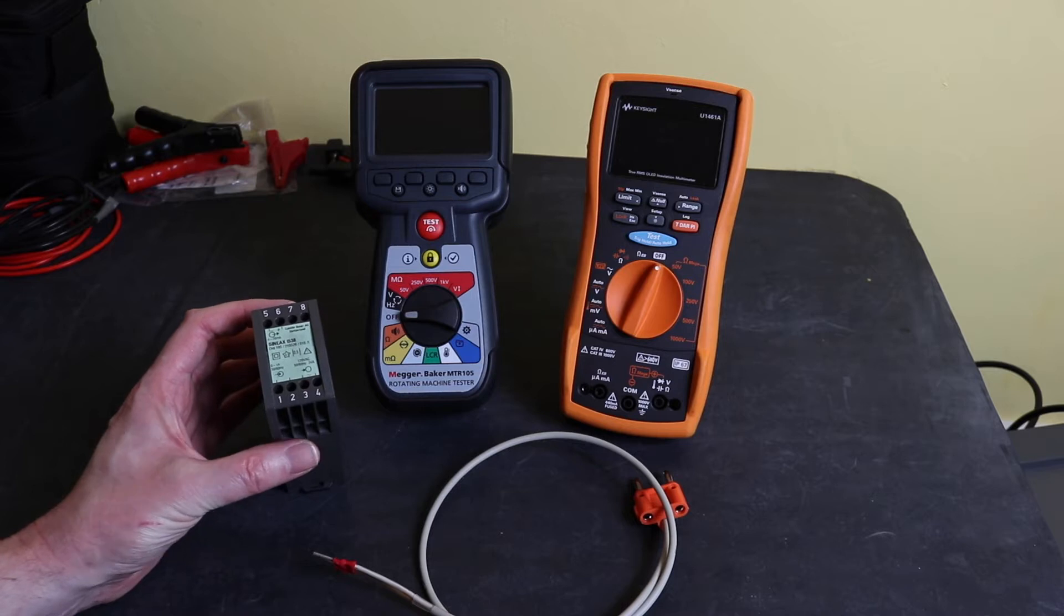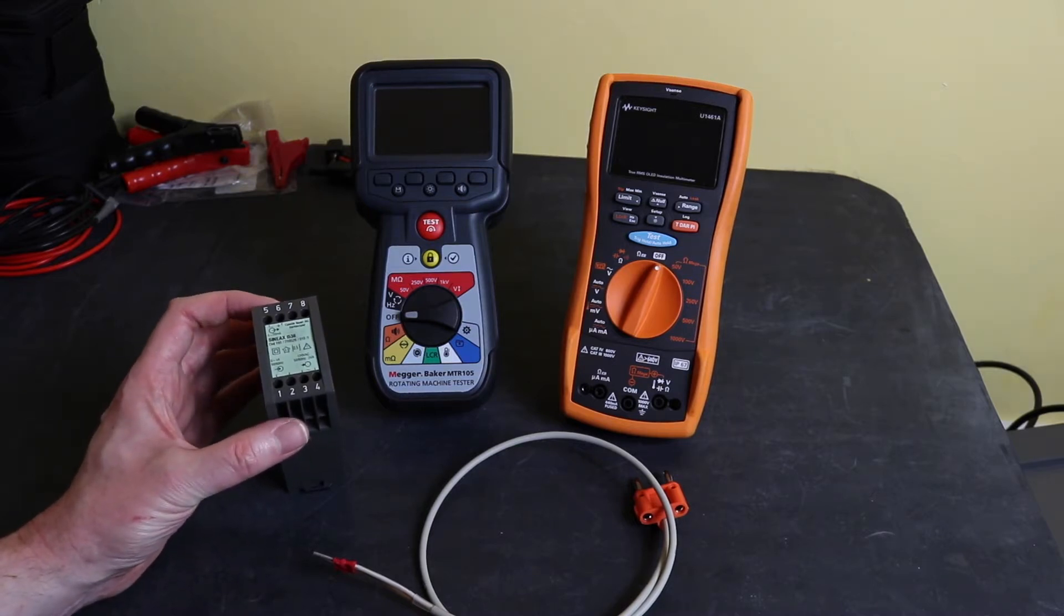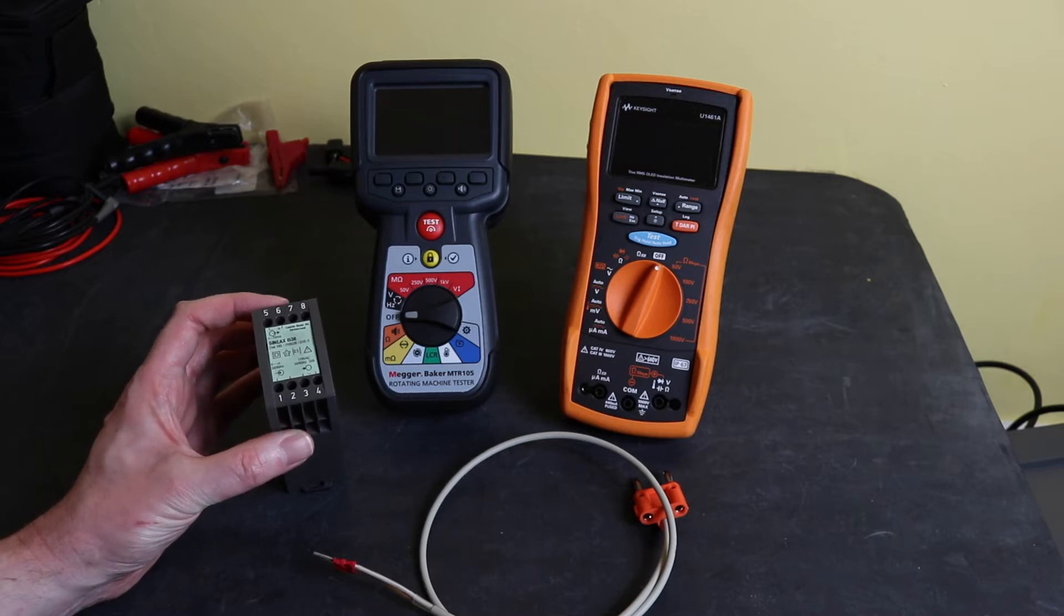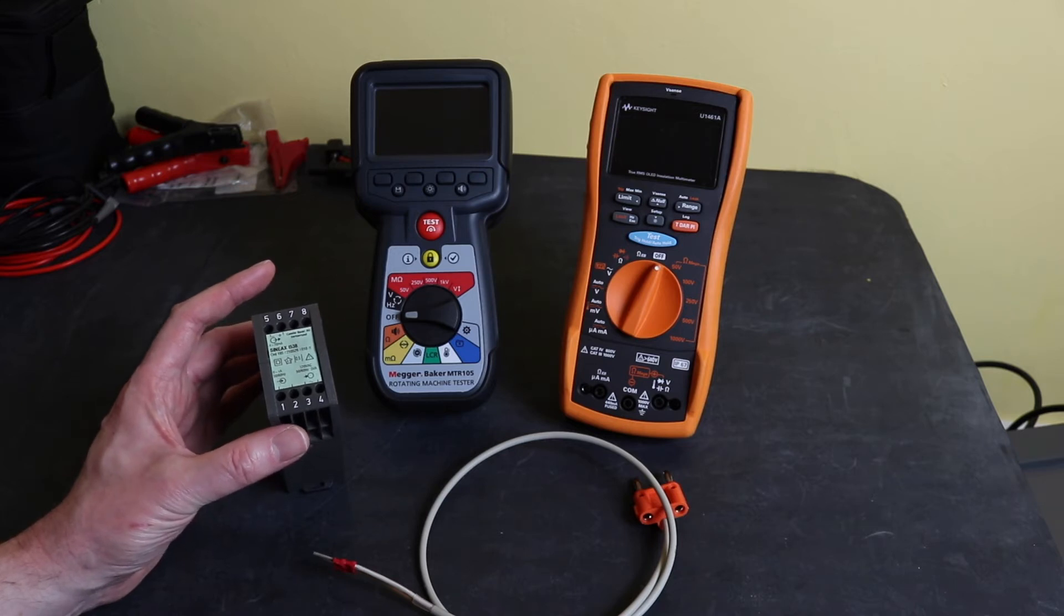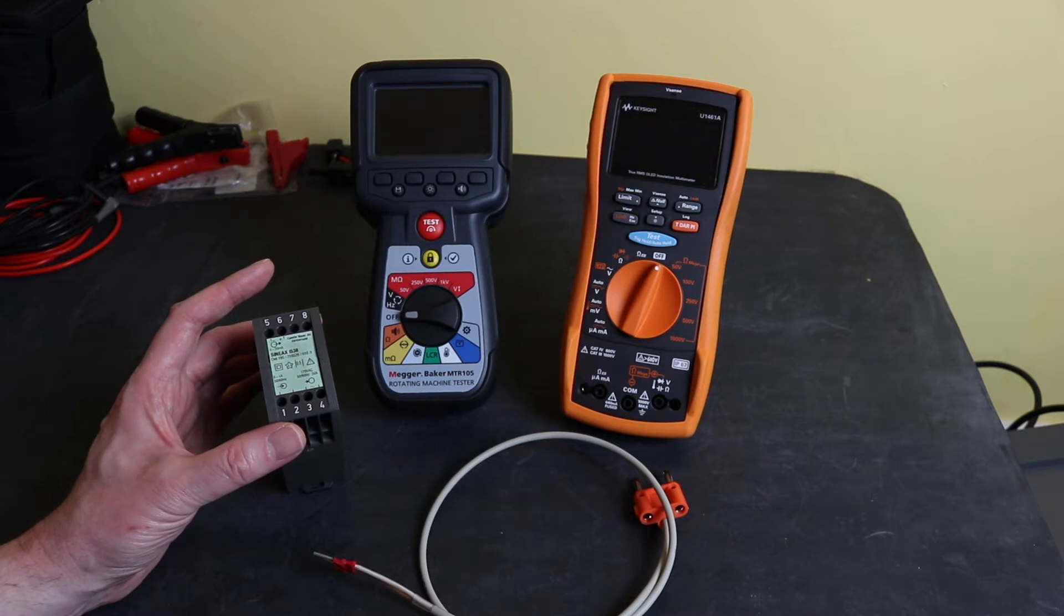It will take the signal from current transformer and put it out in a smaller milliamp signal that the control system will understand. In this case for this one it's 4 to 20 milliamps and that's the vast majority of the ones that I deal with.